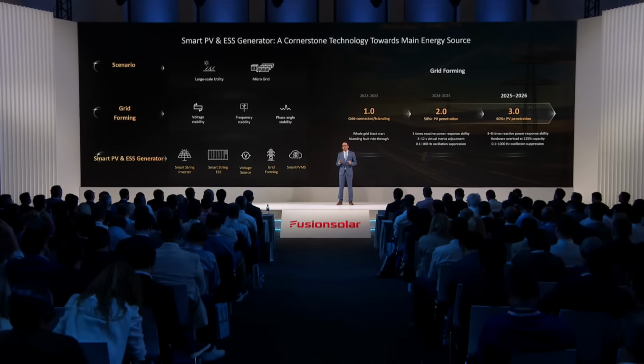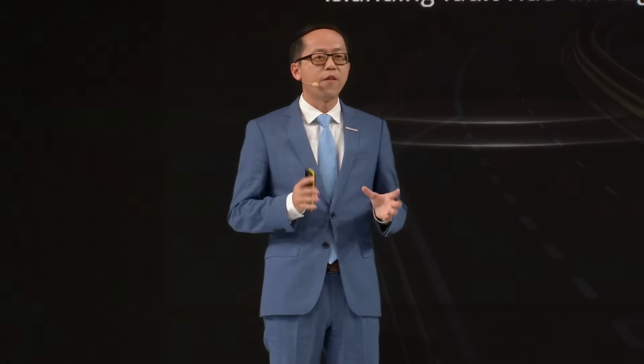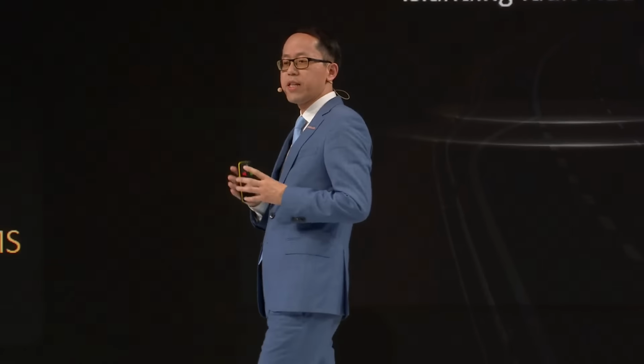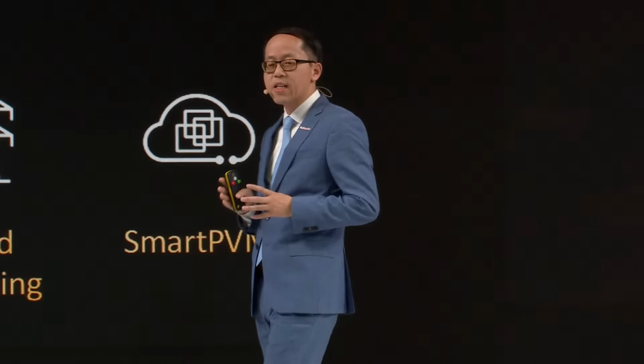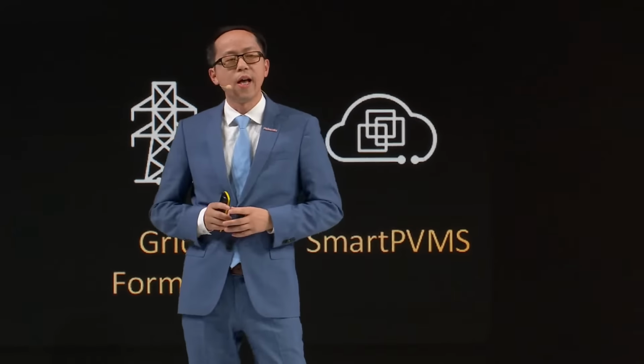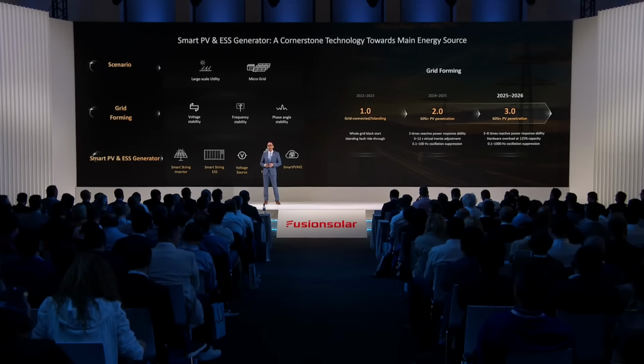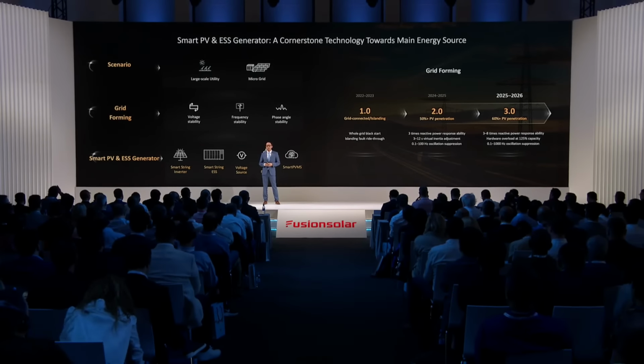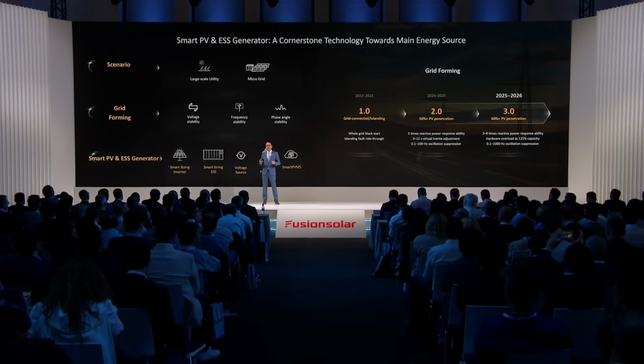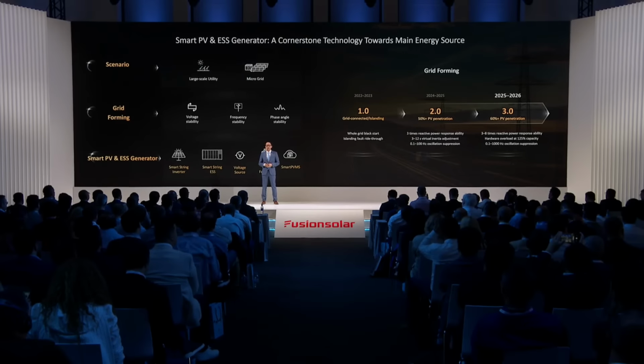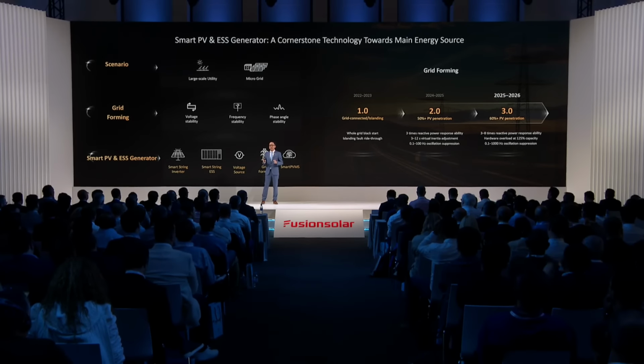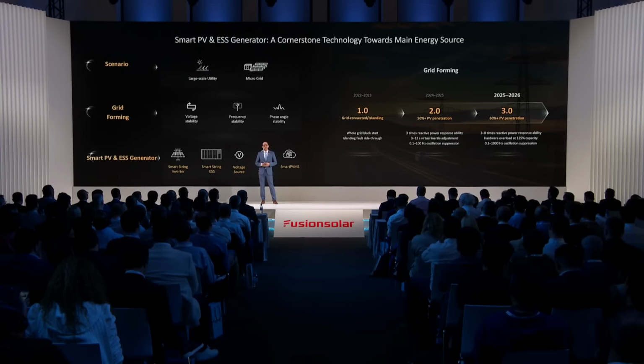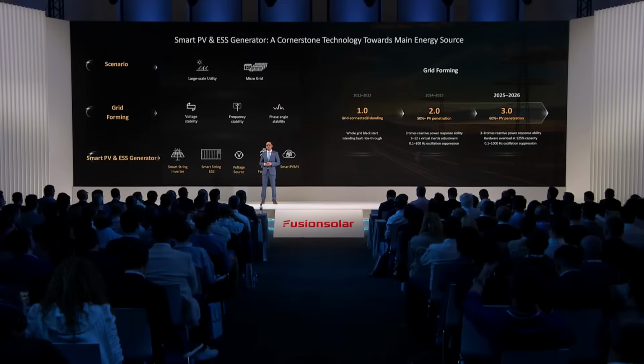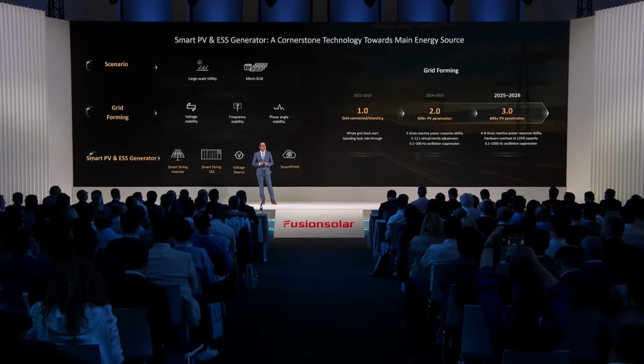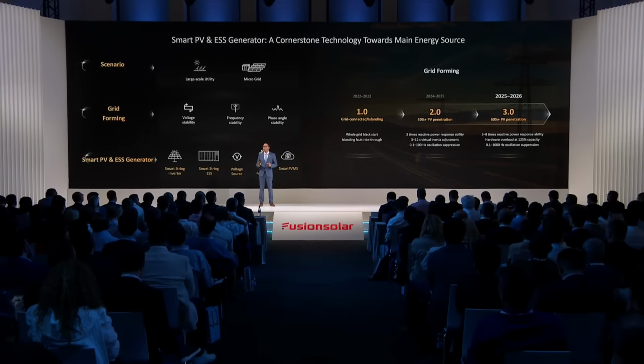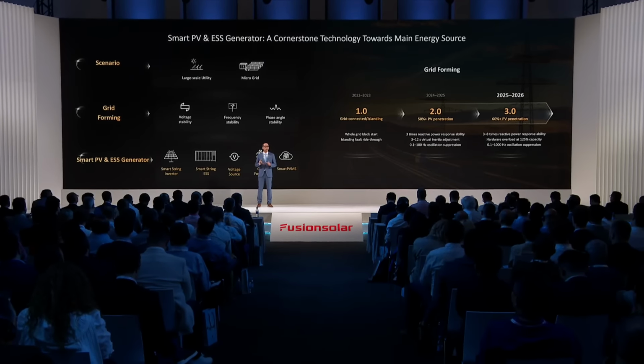We will continue to evolve grid forming in 3 phases. In the first phase, we adopt active grid forming technology to achieve gigawatt-level black start and multi-islanding fault ride-through, enabling a stable and resilient power supply. In the second phase, we can support 3 times reactive power capability, 1.25 times overload capability, 3 to 12 second equivalent moment of inertia, and 0.1 Hz to 2.5 Hz frequency oscillation suppression. Compared with grid following, we support more than 50% high penetration of renewables.